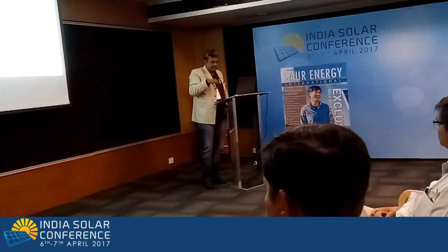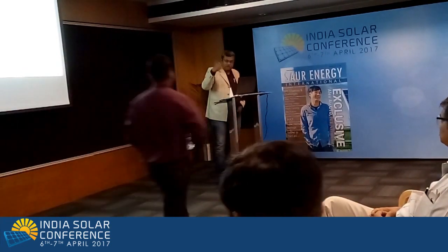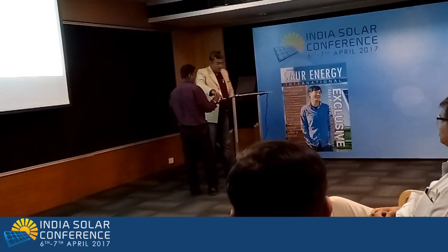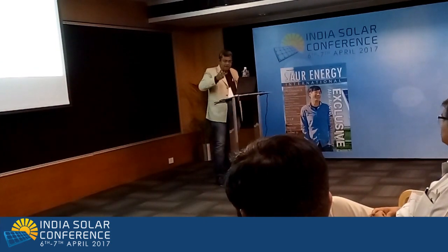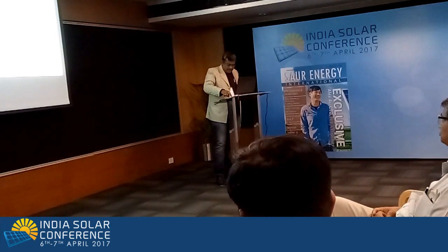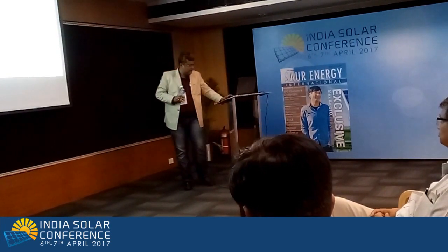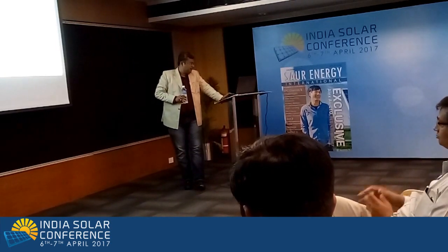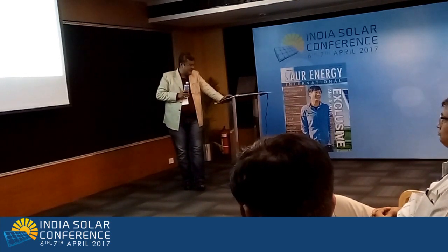The regulation says that today at 10 o'clock in the morning you have to give the forecast of the next day, and you can give the revision every 1 hour 30 minutes starting from today 12 o'clock. So actually you are forecasting 96 time blocks plus the morning 10 o'clock to 12 o'clock period. That is the extra time period you have before making any other revision.